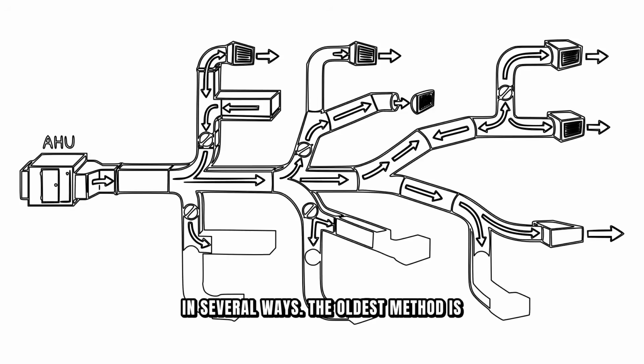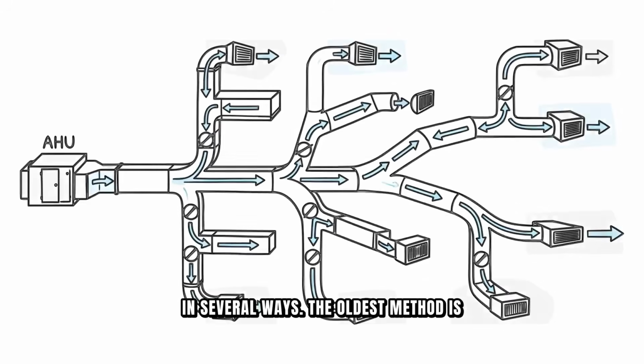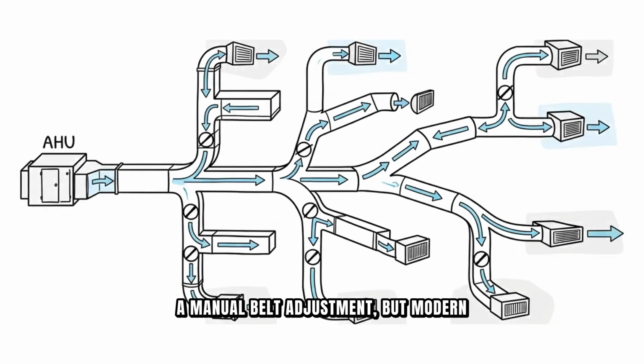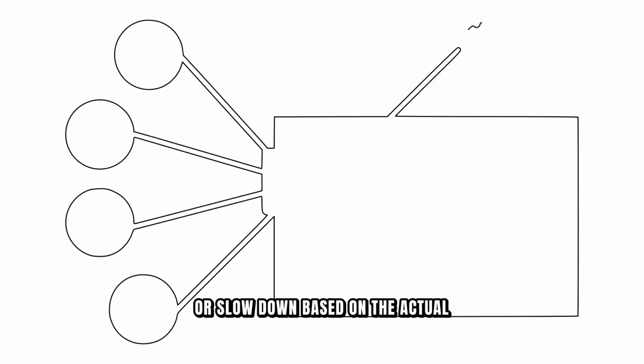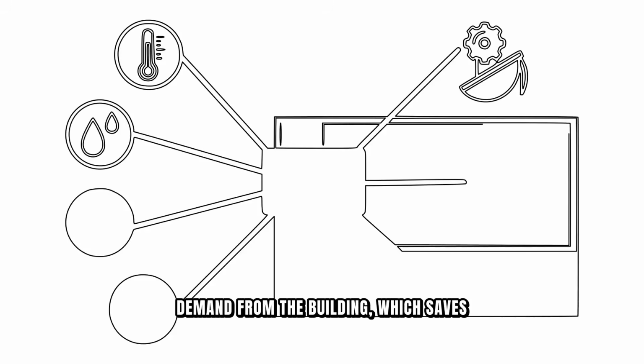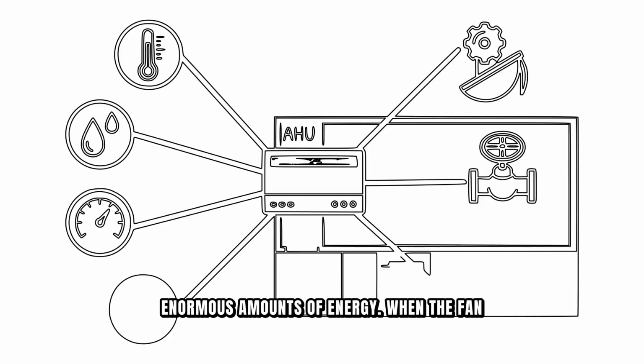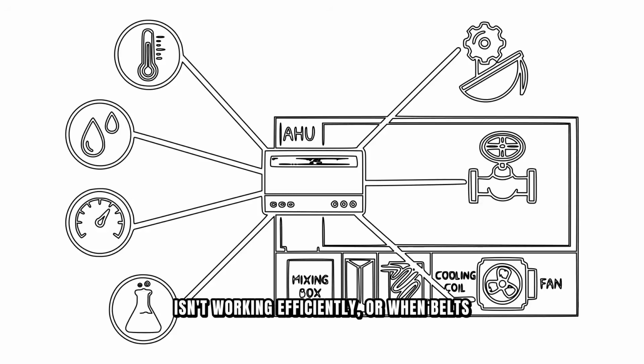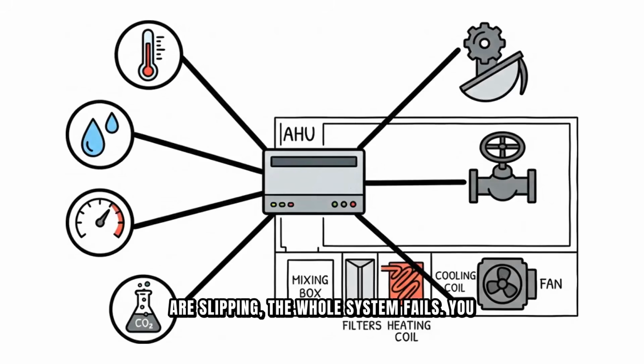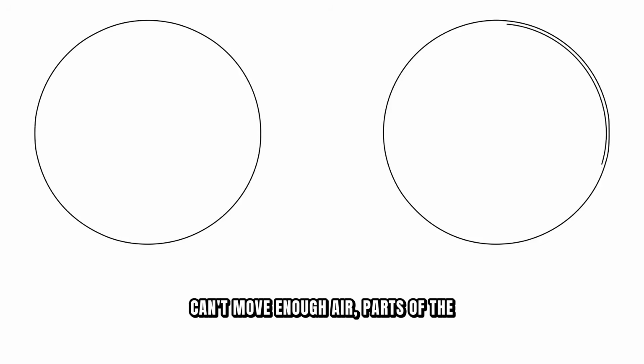The oldest method is a manual belt adjustment, but modern systems use variable frequency drives, or VFDs. A VFD lets the fan speed up or slow down based on the actual demand from the building, which saves enormous amounts of energy. When the fan isn't working efficiently, or when belts are slipping, the whole system fails. You might have all the right temperature and humidity in the discharge, but if the fan can't move enough air, parts of the building stay uncomfortable.